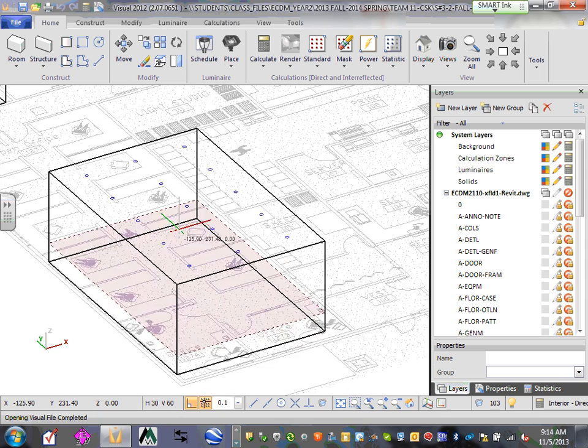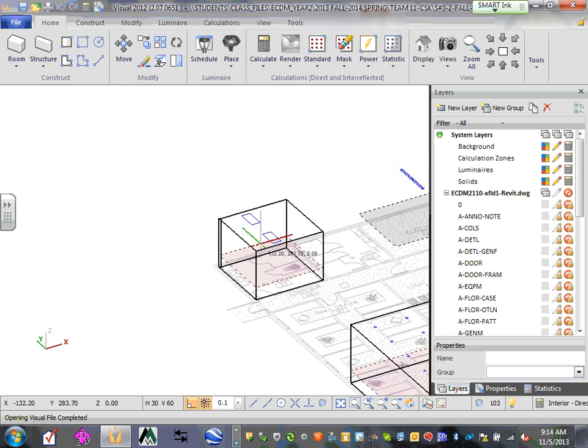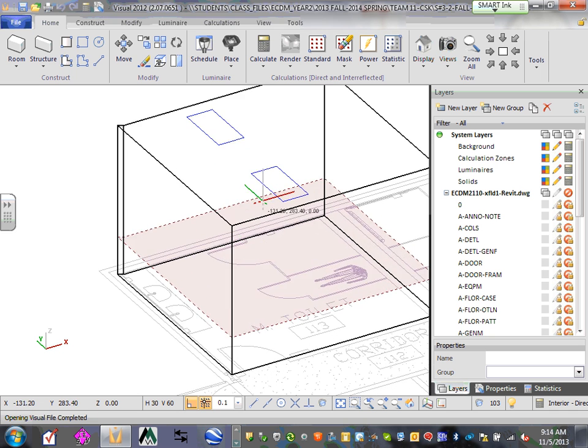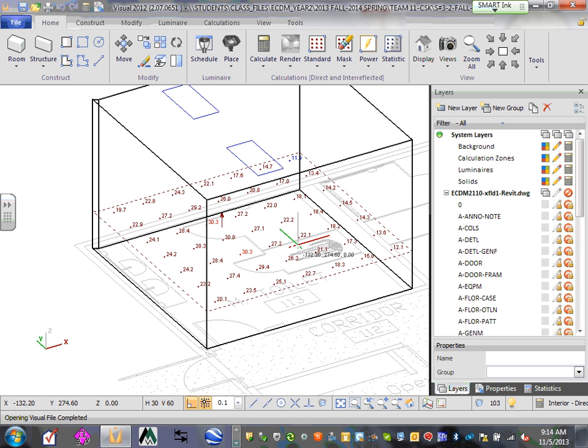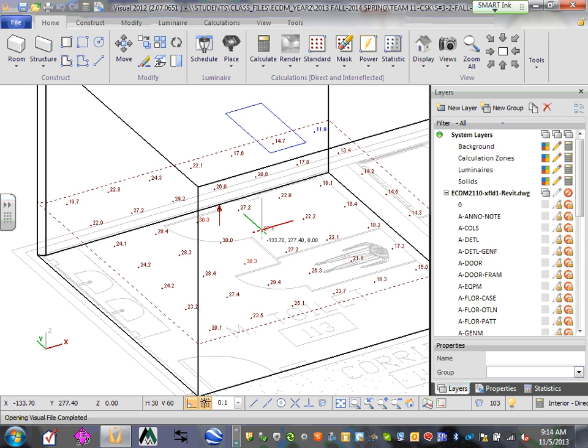Here's a bathroom as an example — we built a box for it and decided to do a lighting calculation. We put two fixtures like the ones above your head in that bathroom, ran the calculation, and came up with all these brown numbers giving you the foot candle values. You can do it by hand, but nobody does that anymore. We use Visual software, and when you work on a commercial or industrial project, you're expected to do a lighting calculation.